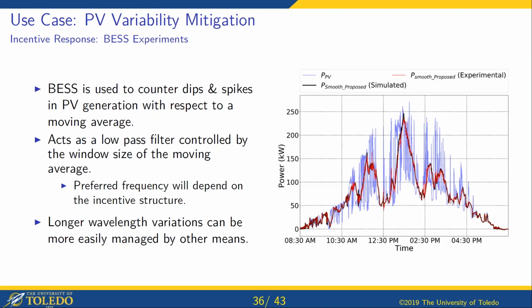The battery system can respond very quickly and effectively to these sorts of things, even without all of that. In fact, this graph is actually showing a different algorithm that we use, which is looking at actual power coming off of the array and using a sliding window on a moving average - when you have a longer window, you have more smoothness. You don't need these large spikes at all if you're willing to spend enough energy from the battery to make up for them.